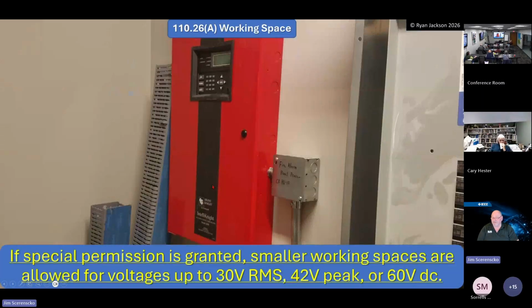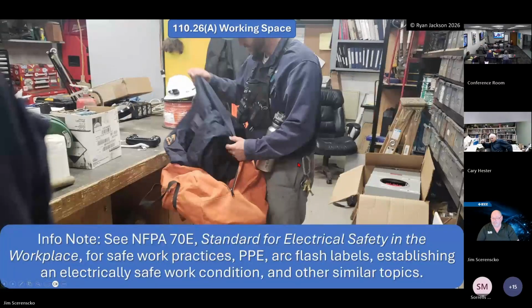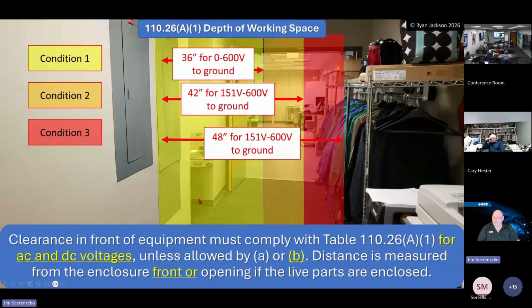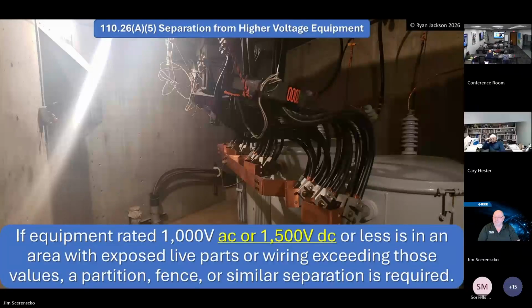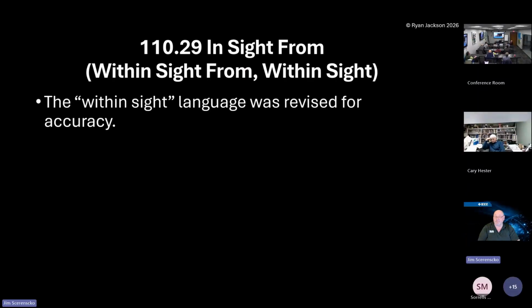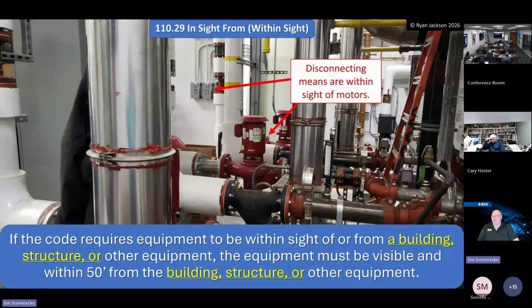And then special permission is granted for smaller working spaces that are allowed for DC voltages. The only time clearance is required in front of a low voltage piece of equipment is a fire alarm panel. And then NFPA 70E, which is the safety standard, gets mentioned in the informational notes. And of course, the clearances, and whether the equipment is rated 1,000 volts AC or 1,500 volts DC or less in an area with exposed live parts. There's what used to be the definition of within sight of.